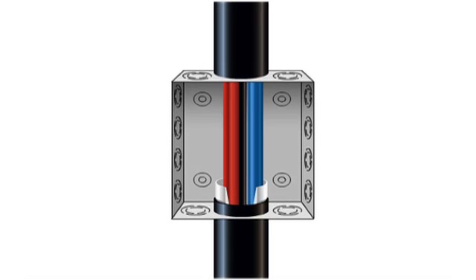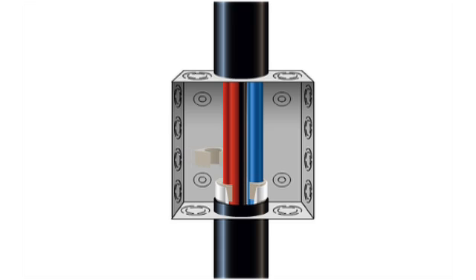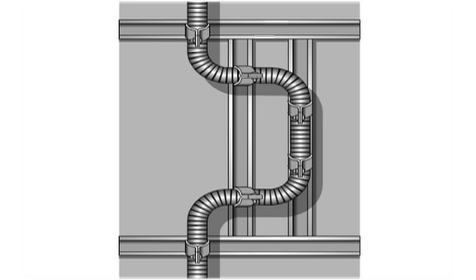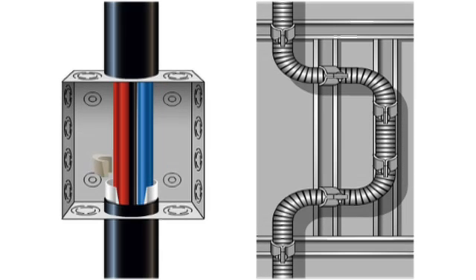Traditionally, contractors have installed cable supports or wedges inside the conduit assembly to support the cables. When installing feeder-sized MC cable, contractors have found that the best way to provide required supports is to place offsets at specific intervals as required by NEC 300.19. Multiple offsets provide additional resistance preventing the cables from sliding in the armor assembly.